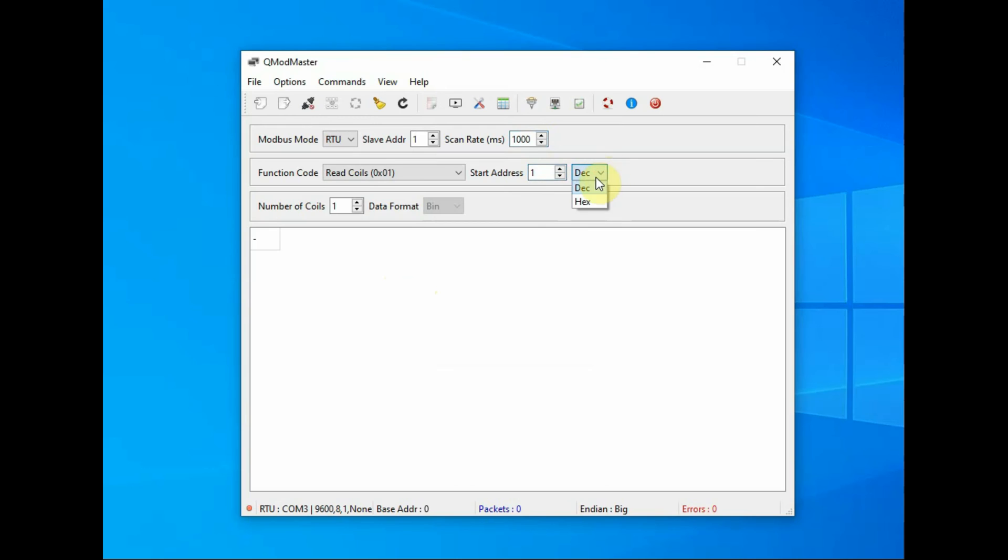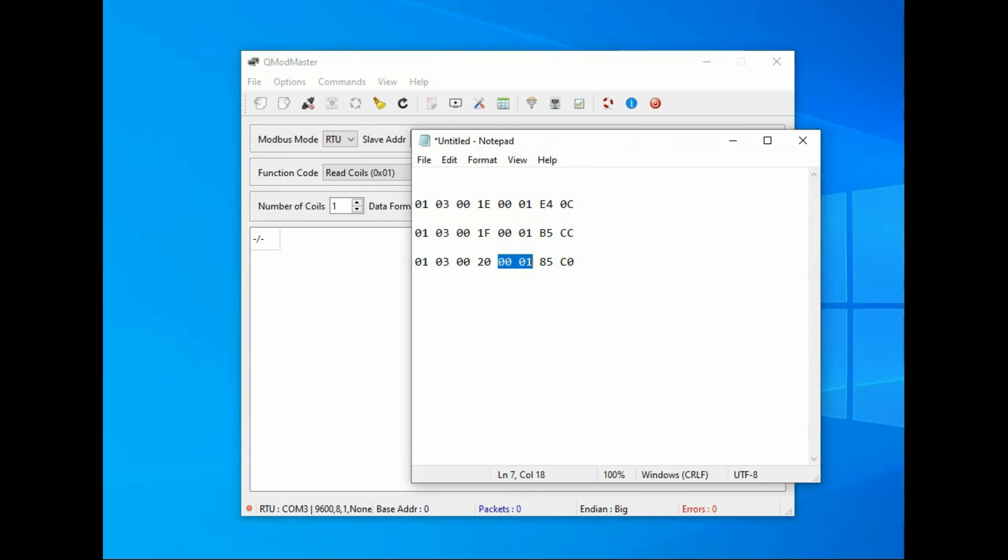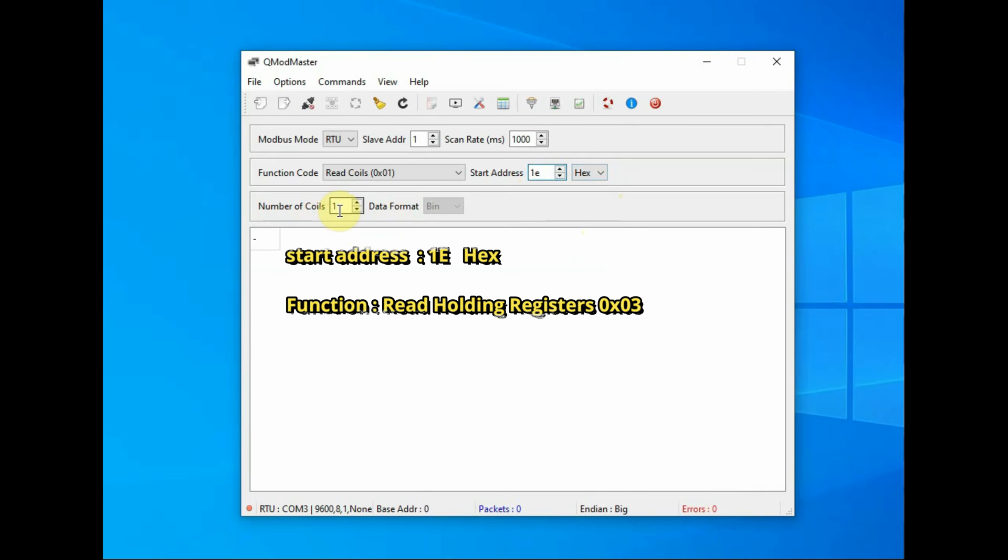The start address is 0x001E, that is the address of the nitrogen value in hex. And then the function code, this is very important, select it as 0x03 which is the function code for reading holding registers in Modbus protocol.